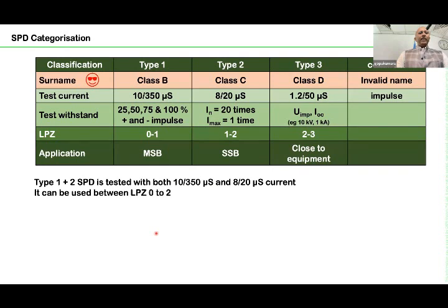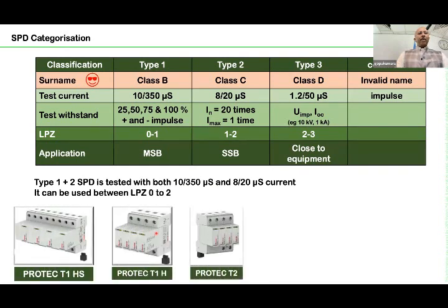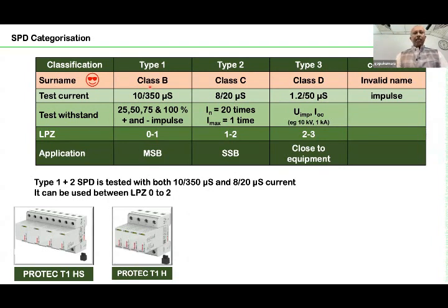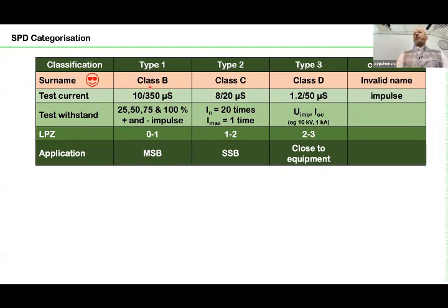Now, where to use these SPDs and what are their names? For example, earlier, people used to ask, I want a class B SPD, a class C SPD. These were names included in the German standard a few decades back, because Germans were the first to come out with a proper standard, so those were used internationally. As a result, people started calling these devices class B, for example. Now the name is type 1. Type 1 is an SPD which is tested for 10/350 microseconds. You can see here, test current 10/350 microseconds.